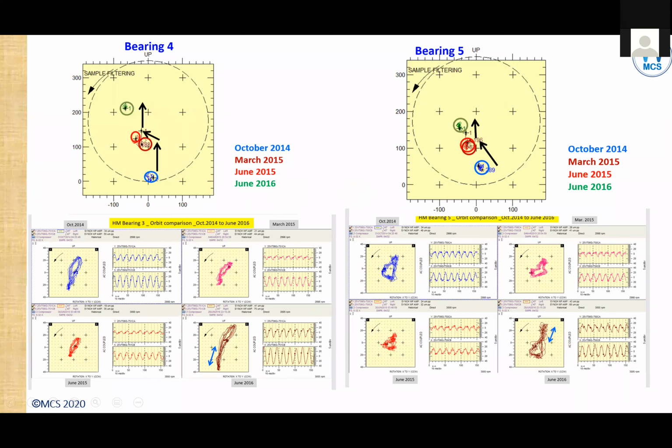So ultimately, when the machine was stopped and found out of alignment, I don't remember how much the values were, but they realigned the machine. So this is the story of the machine, and this is how the shaft center line plots show it. If you only look at the overall vibration plot and the spectrum, trying to look for 1x and 2x, for turbo machinery those are not the plots to judge the alignment conditions. You need to look at the shaft center line movements and the gap voltages, how they are moving. They give you a good picture about what is happening on the machine.